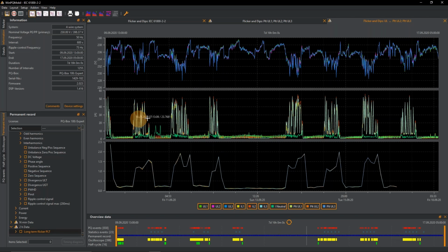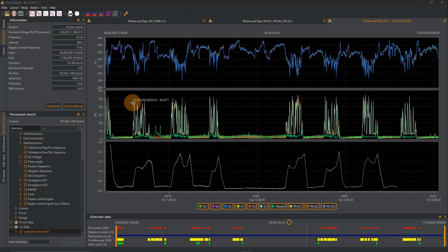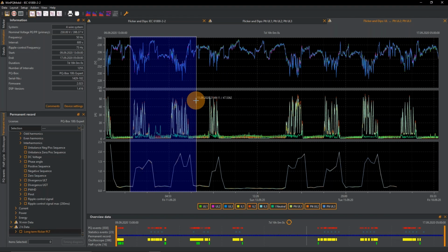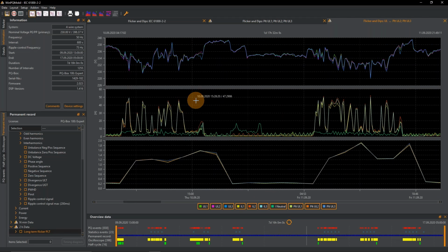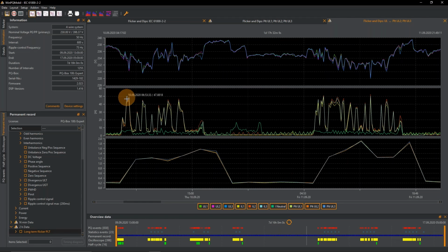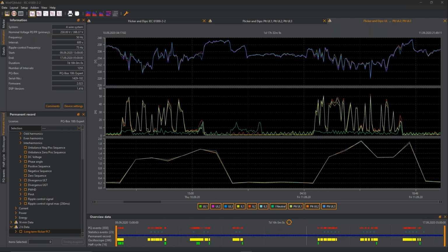And here I can see, okay, every time the customer ran his business, there was some current we measured, and the long-term flicker rose again. But when I zoom in a little bit, I just click and hold the left button of my mouse, and I see, okay, there was something going on, but it doesn't seem really dramatic. We have maximum values of around 50 amps, and I know that the customer had a main fuse in this entrance rated for 63 amps. So there shouldn't be a problem, right?